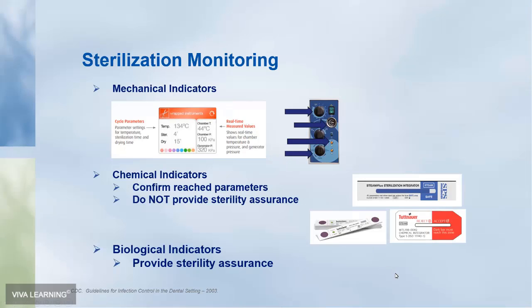We now look more closely at sterilization monitoring. Mechanical indicators, chemical indicators, which I'd already mentioned, and biological indicators are the three types of sterilization monitoring that we should use. The mechanical indicators used to all be analog. They're mostly digital now, and you can see a couple of examples here. The one on the left is a digital, and you can see the cycle parameters here. They've got the temperature, here we've got the chamber temperature, we've got the chamber pressure as well, and we've got time too. So those are the parameters.